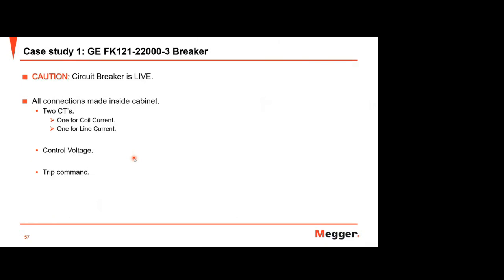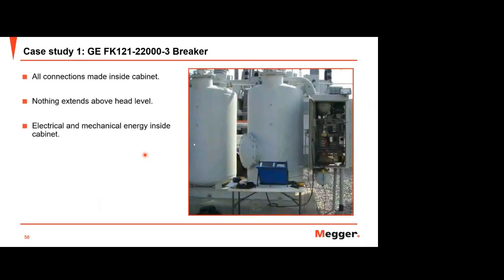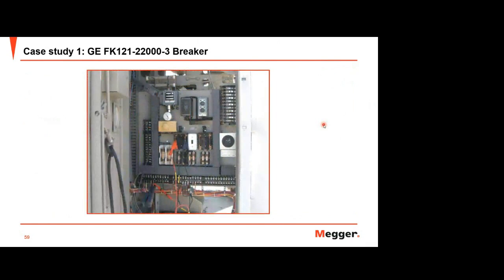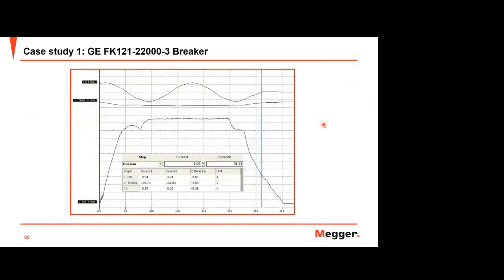The breaker is live, with all connections made inside the cabinet: two CTs, one for coil current and one for line current. We measure control voltage and connect the trip command. So this is the connection example. We connect here in the cabinet, and this is the sample connection for voltage measurement. And this is the result that we have here. You can see this is the trip coil profile, and this is the load current here. We can consider this as the main contact time, and this is to analyze the tripping coil current, with how much peak current and the total length.